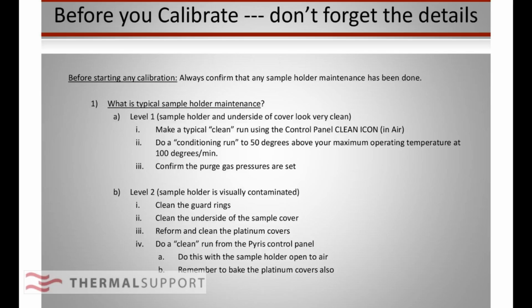A couple of decades ago, I worked on an instrument. I came up being a service guy and then went on and did other stuff. And I worked on this instrument. The sample holder was trashed, and I had been there before for routine maintenance, and it was dead on. It worked beautifully, and they just trashed it. Somebody came in and ran the wrong material, ran too much of the material, and it overcame the system and contaminated the sample holder. And it had been well within the 0.1 degree accuracy and precision test and on the delta H numbers before, and it was well off.